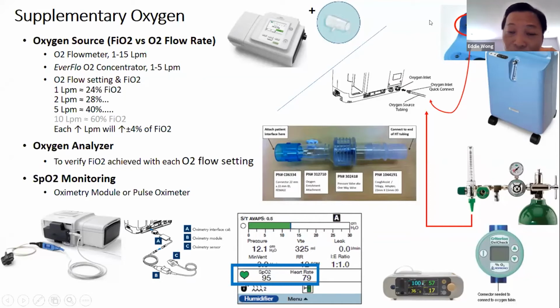If you get this EverFlo concentrator, this machine can only deliver 1 liter to 5 liter of oxygen, which is equivalent to 40% FiO2. Normally, patients are only allowed to go home if they are not dependent on more than 40% FiO2. If the patient in ICU is using a ventilator, for those acute patients, they can use FiO2 up to 100%. So if the patient is still dependent on more than 40%, normally they are not fit to go home. They must stay in the hospital. That's why a concentrator up to 5 liter is fit for staying at home. But if you need higher oxygen, you need to go back to hospital.